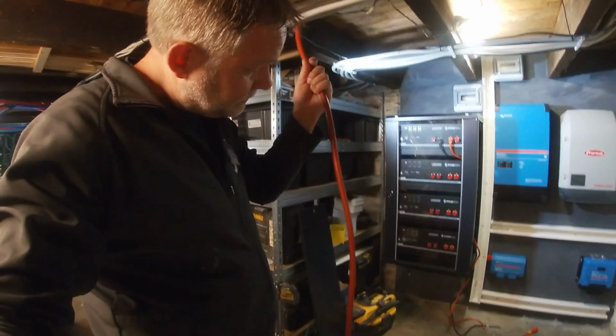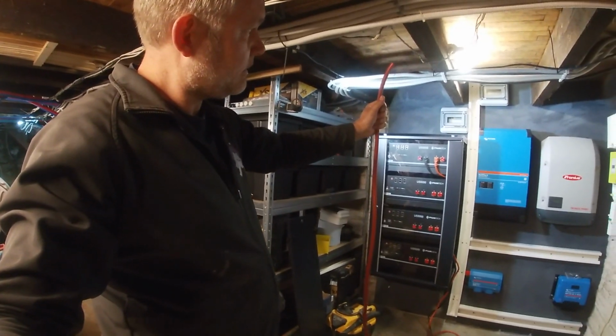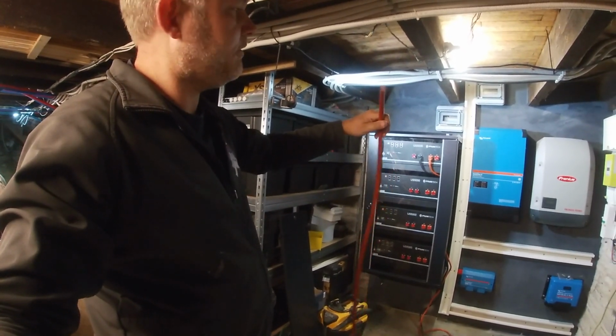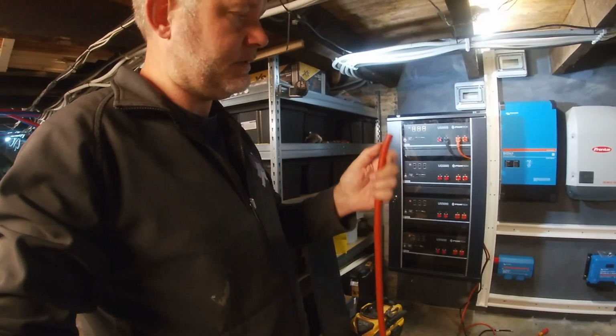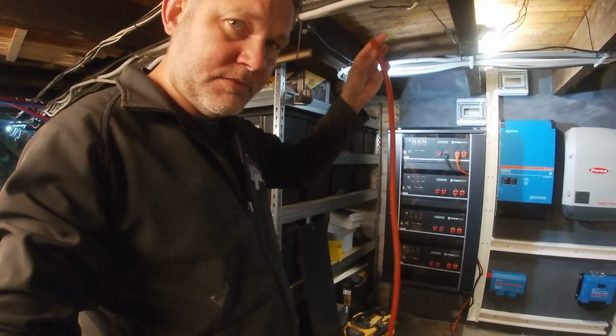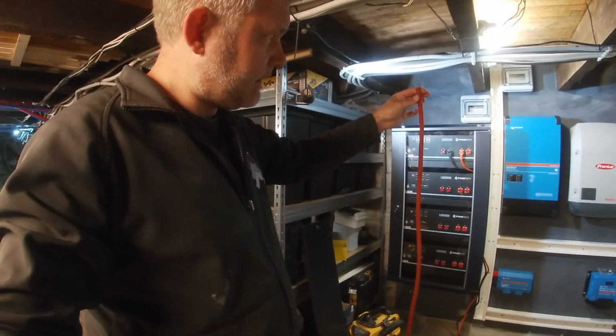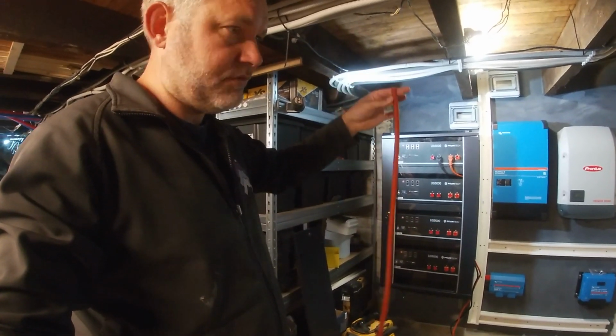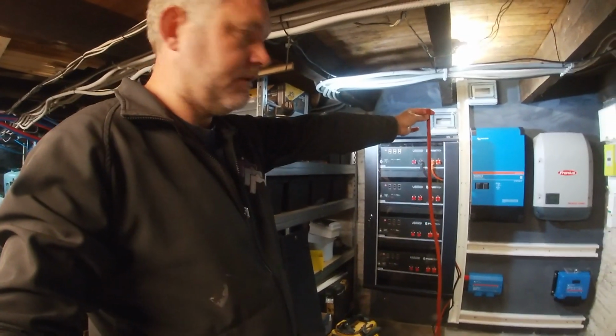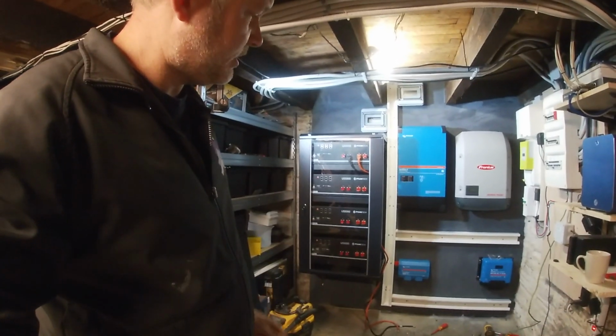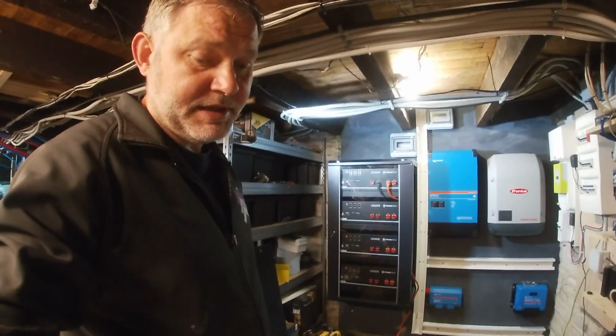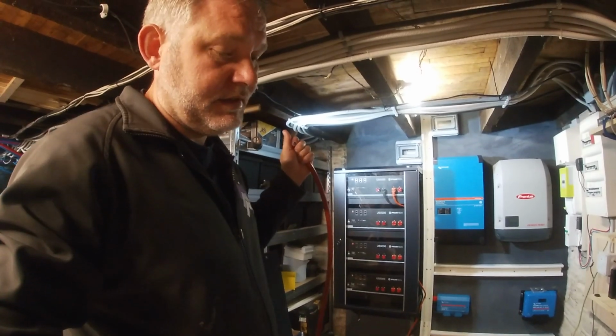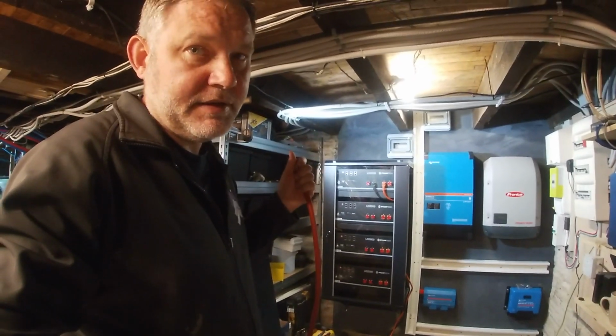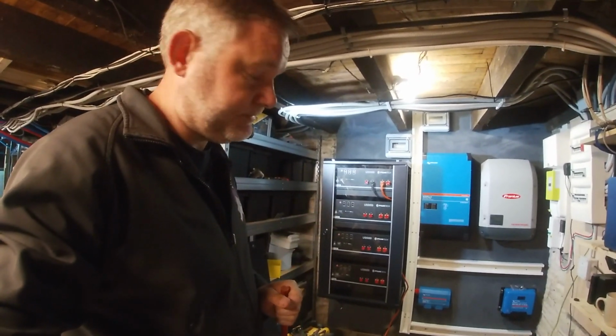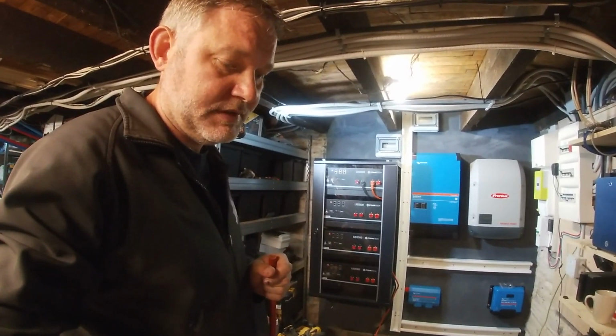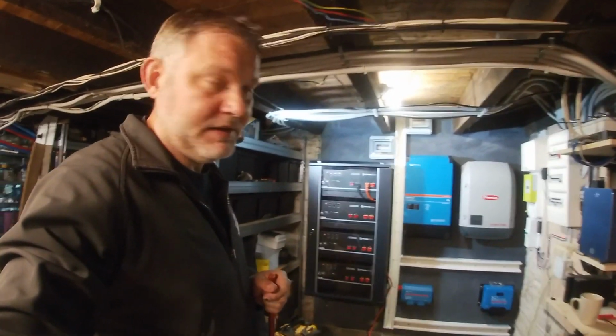Here's one I prepared earlier. This is a 50 square millimeter cable, and I need 2 of these in red and 2 in black to go and power the main multi-plus inverter as per the manual. A lot of people undercable their inverters, so always read the manual and use the correct thickness cable. Saves burning the house down later on, obviously.